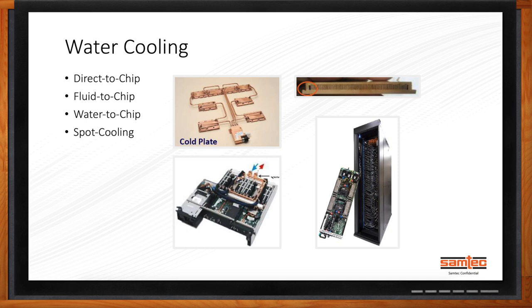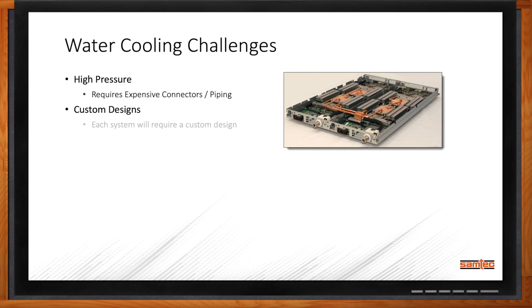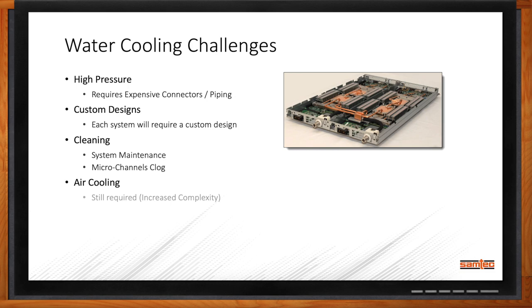Water cooling has very specific challenges: you have to run a lot of pressure through the system; you still need something to cool the liquid running through the system, which means additional cooling units; every system is a custom design; you have to continually clean the system or your efficiency goes down and the micro channels will clog up; and once again you still require some air movement to cool the rest of your components.